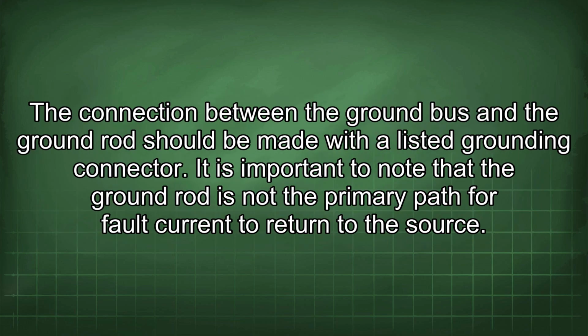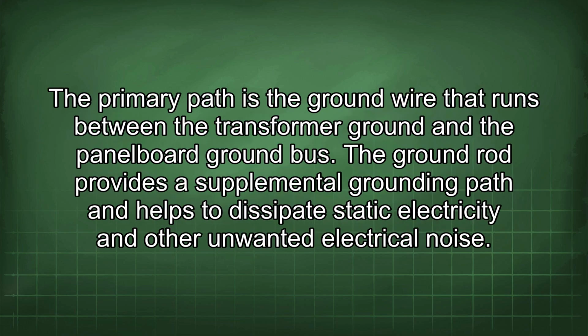The connection between the ground bus and the ground rod should be made with a listed grounding connector. It is important to note that the ground rod is not the primary path for fault current to return to the source. The primary path is the ground wire that runs between the transformer ground and the panelboard ground bus. The ground rod provides a supplemental grounding path and helps to dissipate static electricity and other unwanted electrical noise.